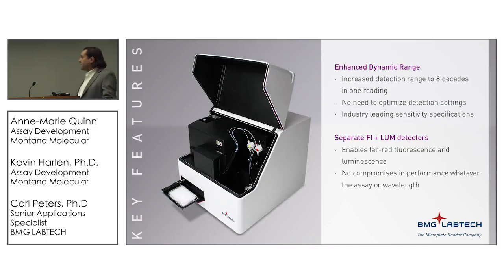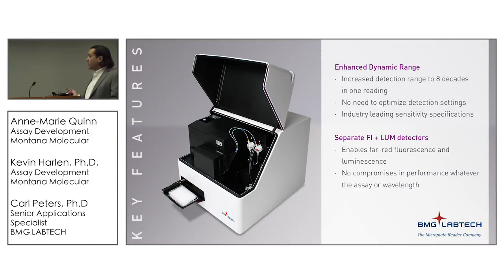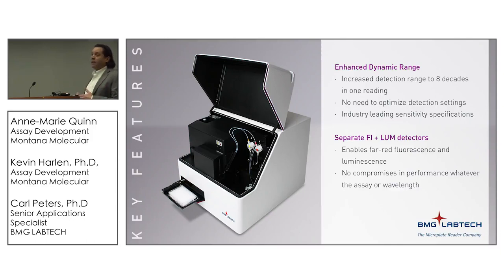The advances in the ClarioStar Plus include enhanced dynamic range, which will eliminate the need for manually pre-setting the gain. This allows the instrument to look at multiple different gains for every well, increasing the detection range up to eight decades in one reading. So you can look at low and high signals in the same well without optimizing settings ahead of time — you literally just put the plate in and start reading, while maintaining the industry-leading sensitivity specifications of the original ClarioStar.